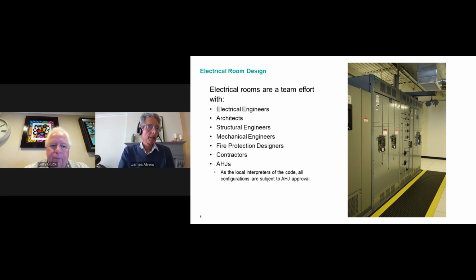Okay. I'd like to begin with some basic reminders regarding electrical room design, since space is obviously one of the biggest issues for generator switchboards. Keep in mind, it's a team effort. Therefore, it's crucial to involve all the members of the project construction team to ensure the equipment as configured has the proper working clearances, access for conduit and busway, and so forth, required overhead clearances. You need weight and mechanical support, obviously proper access and egress.